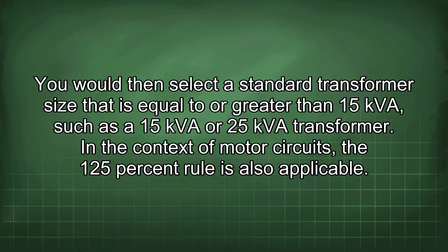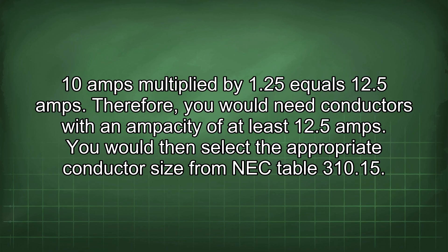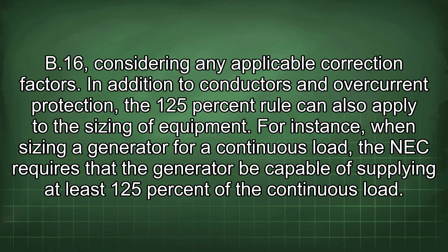In the context of motor circuits, the 125% rule is also applicable. When sizing conductors for a motor circuit, the NEC requires that the conductors have an ampacity of at least 125% of the motor's full load current rating. If a motor has a full load current rating of 10 amps, multiply 10 amps by 1.25: 10 × 1.25 = 12.5 amps. Therefore, you would need conductors with an ampacity of at least 12.5 amps, selected from NEC table 310.15(B)(16) considering any applicable correction factors.